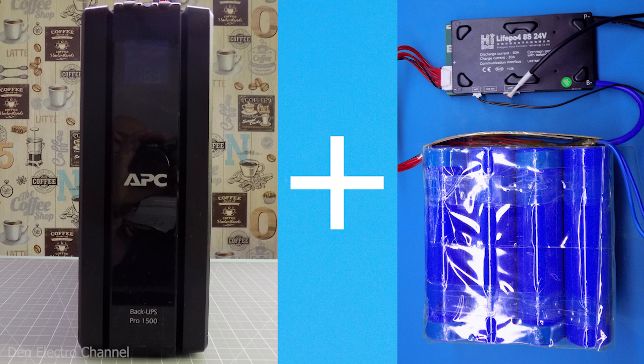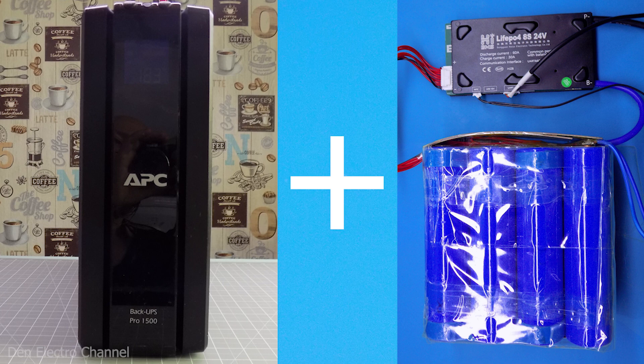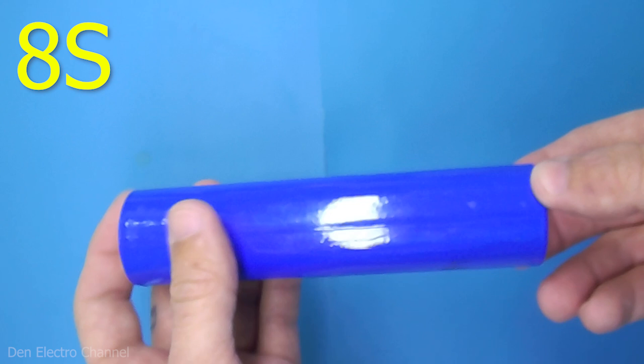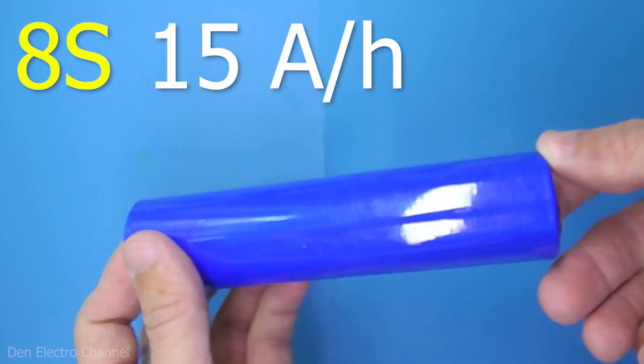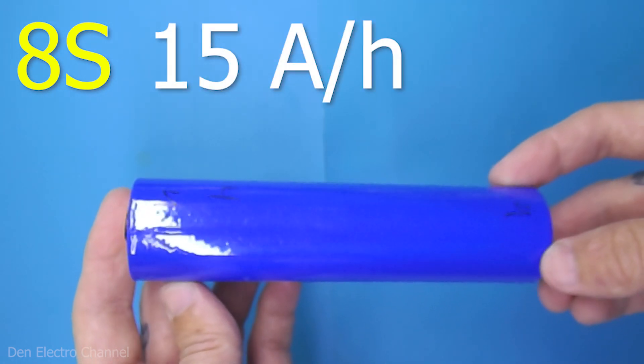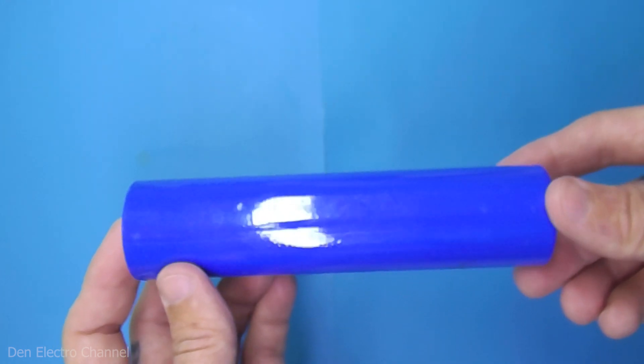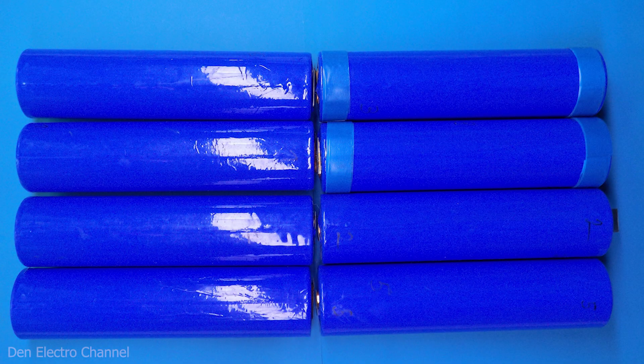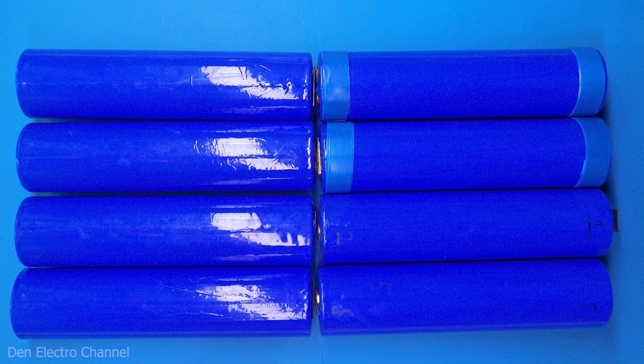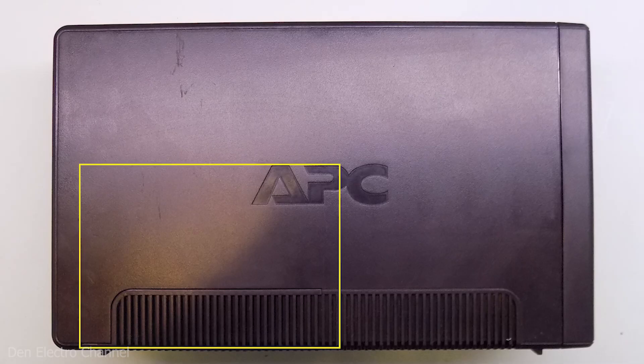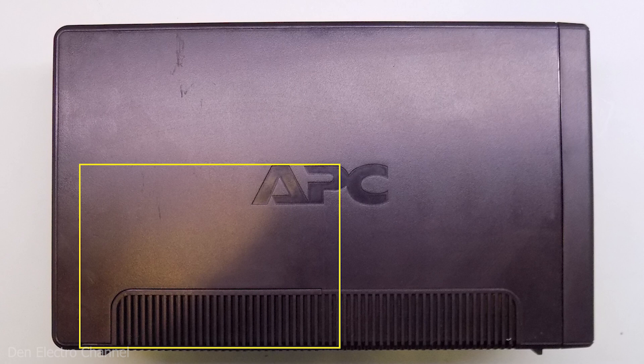I'll start with batteries. 8 lithium iron phosphate batteries will be used here, each with a capacity of 15 amp hours. The nominal voltage of each such battery is 3.2 volts. Therefore, to get 24 volts they must be connected in series. In UPS, the battery compartment is located here. 2 batteries were installed vertically.